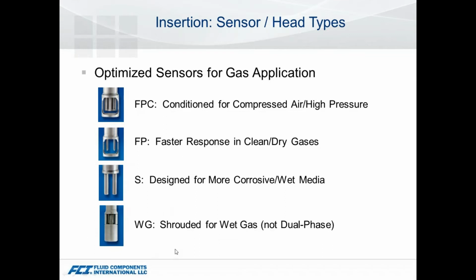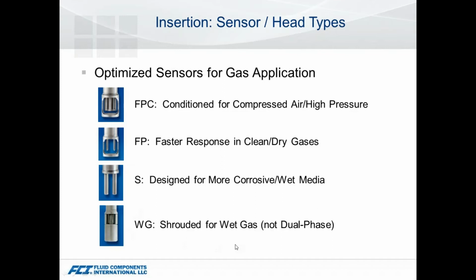And then recently we introduced one of our best kept secrets that we've been doing as specials, but we've standardized on it now and made it a standard offering, is this wet gas sensor. This wet gas sensor is designed really as a mechanical knockout. It's not really set up for dual phase, but it is a way that if you've got some moisture in your process, one way of handling that issue. We'll talk about it a little bit more later on here.